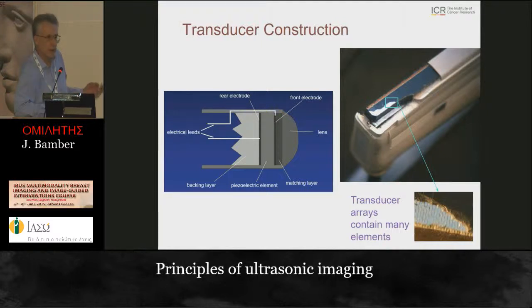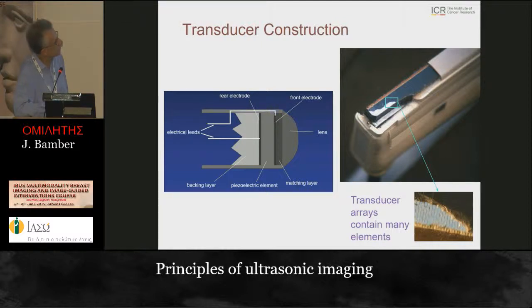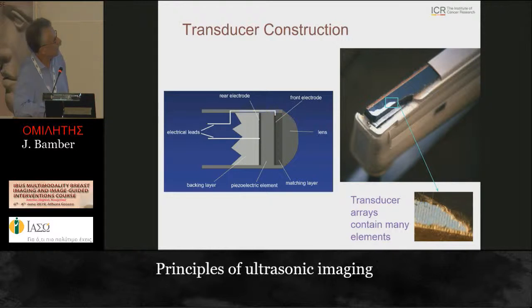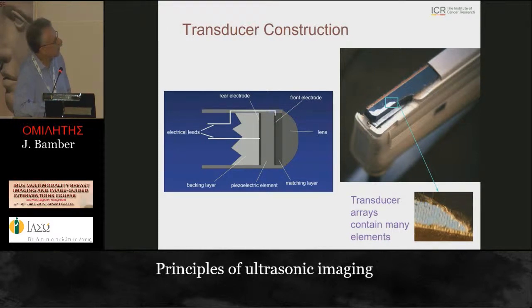A typical ultrasound transducer has that piezoelectric element inside with electrodes on front and back connected to cables for voltage excitation. In front there's an acoustic lens of different refractive index - a different speed of sound to the tissue - so the sound wave can be bent and focused in one plane. In the other plane, the transducer is divided into tiny elements. I've taken apart an old non-working transducer so you can see inside: you can see the rubber lens and the tiny strips - these are microns in size.